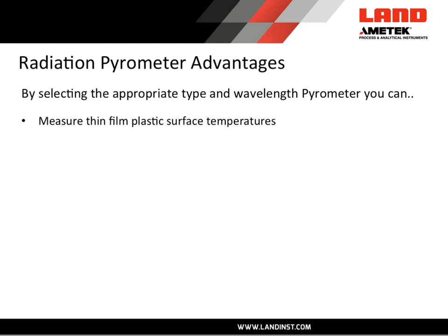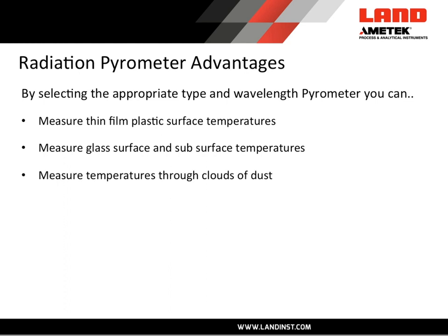For instance, you may choose a wavelength that will see thin film plastics like saran wrap as completely opaque, and simply by looking at them you can measure the temperature without damaging the surface. You can measure glass surface temperatures. By choosing the wavelength you can also measure subsurface temperatures, which is not possible with a contact device. You can measure temperatures through clouds of dust.